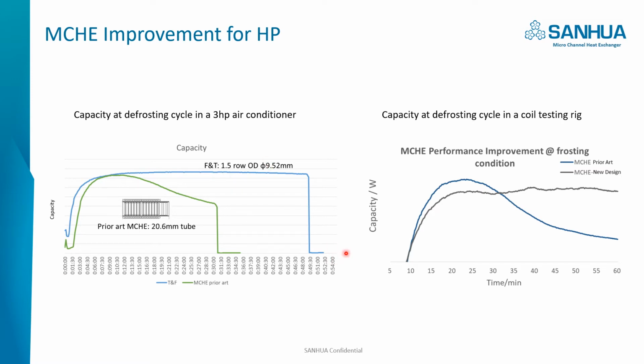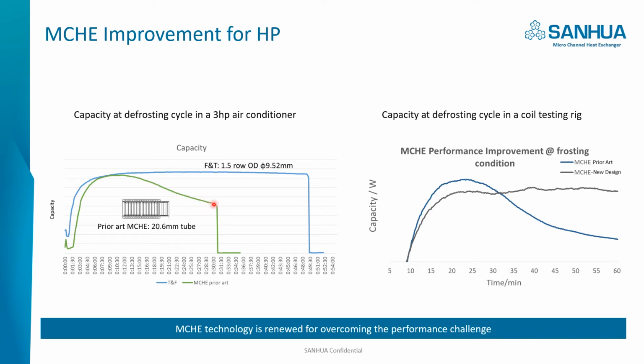Let's see the iteration design of microchannel for the heat pump. Previously, we used the 20 mm microchannel tube design to compare to the 1.5 row 9.5 mm fin tube heat exchanger. The rated cooling and heating performance are very close, but under the frosting condition, the green curve is microchannel. The peak points are very close, but the deterioration of the microchannel is much faster than the fin tube heat exchanger design. And recently, we developed a new microchannel design to gain performance under the frosting condition.